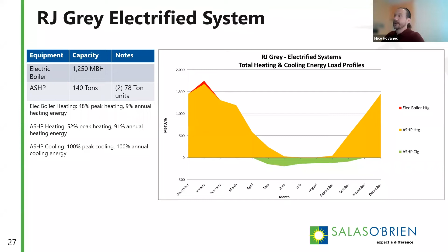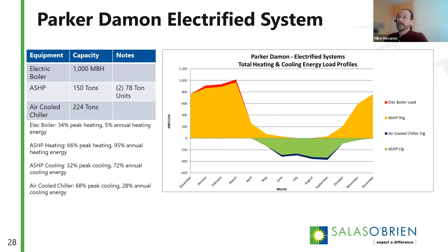For the Parker Damon building, the electrified option is more of a hybrid approach, where we have air source heat pumps optimized for the majority of the heating and cooling loads. However, we have a remaining peak cooling condition and peak heating condition that need an additional HVAC asset. For the cooling, we've suggested an air-cooled chiller, and for the peak heating load, we've proposed an electric boiler.